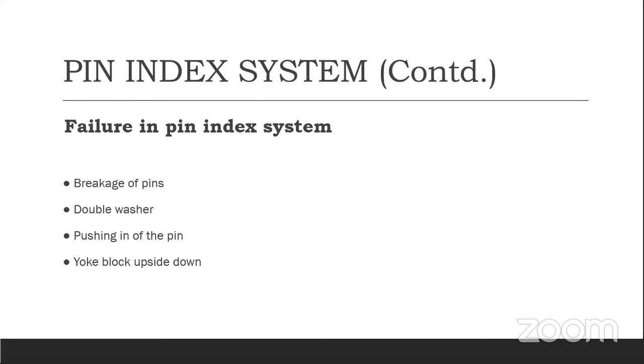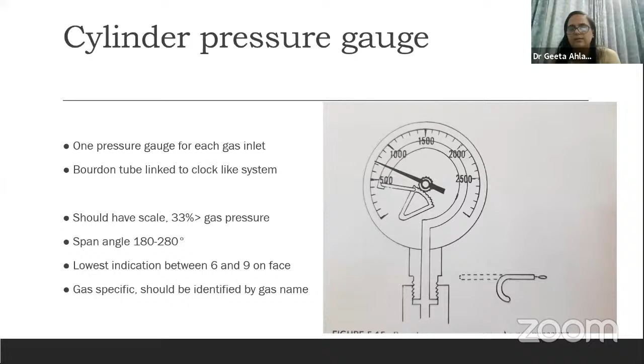Then we talk about the pressure gauge. Now you have a cylinder, but you should know all the time how much pressure it has. So Bourdon's pressure gauge was the one which was initially used. These pressure gauges had tubing which was coiled, and it would straighten up as the cylinder pressure increases, as you can see. This was connected to a needle which will show you from outside how much pressure your cylinder has. But apart from this, it was also at an angle which you could see, and it was color coded always. Now in the modern machines, color coding is there, but the gauges are fixed on the upper part of your machine.